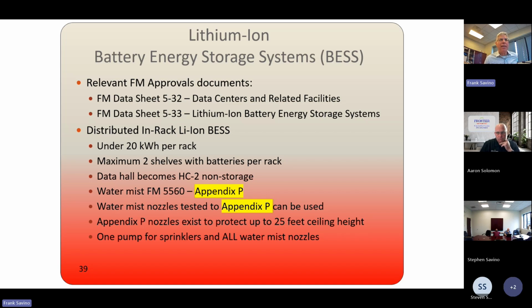So this basically is saying you have to have less than 20 kilowatt hours per rack. That's where your water mist approval restriction is. No more than 20 kilowatt hours per rack and no more than 2 shelves with batteries per rack. Then your 5560 Appendix P can be used. But if you have more than 20 kilowatt hours in a rack or more than 2 shelves, you cannot apply Appendix P of 5560.